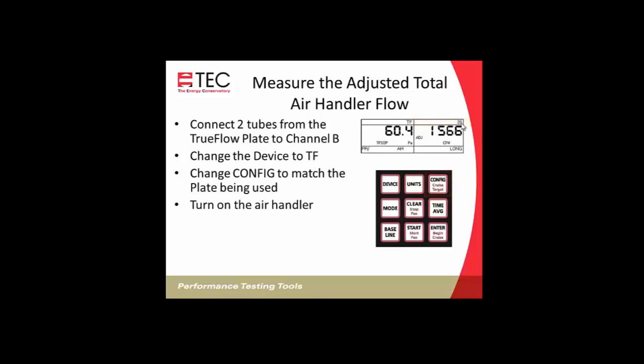Next, we'll turn on the air handler. If our numbers are fluctuating, so if our flow numbers on this side showing 1566, if those numbers are fluctuating, we'll click the time average button and we'll toggle through from 1 to 5 to 10 to long. And we'll leave it at long-term average until our flow number is pretty stable. And once that stays the same for a few seconds, we can either push hold or we can write down that number. Either way, we'll need to write it down because the DG700 doesn't store numbers.